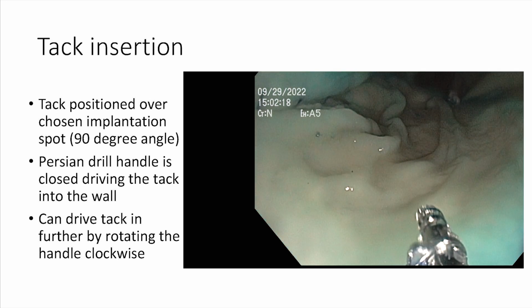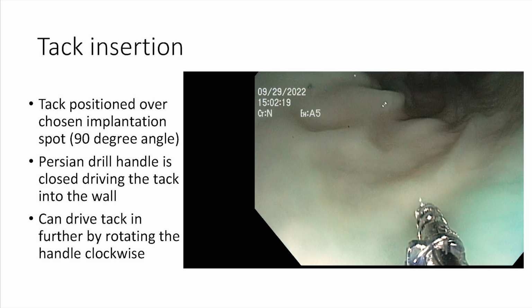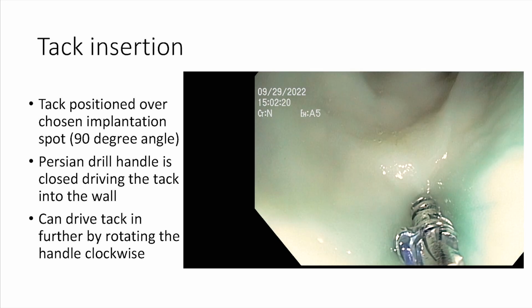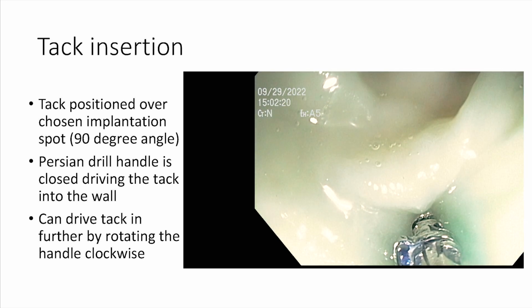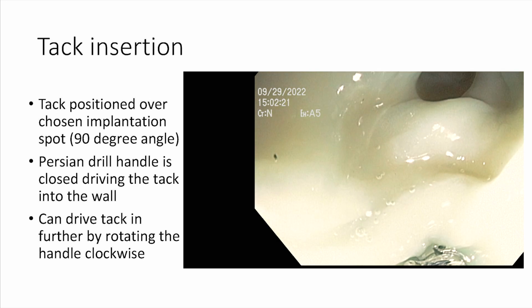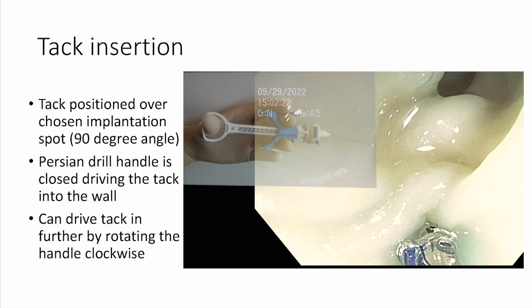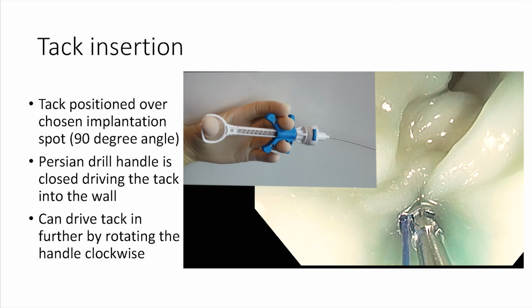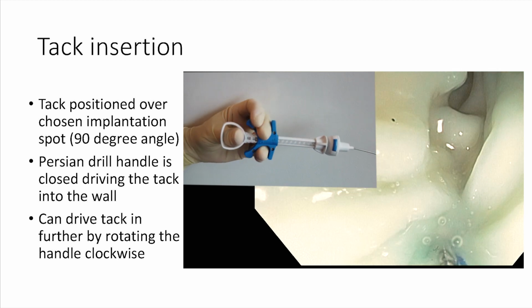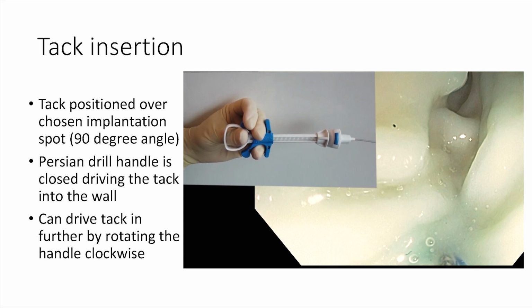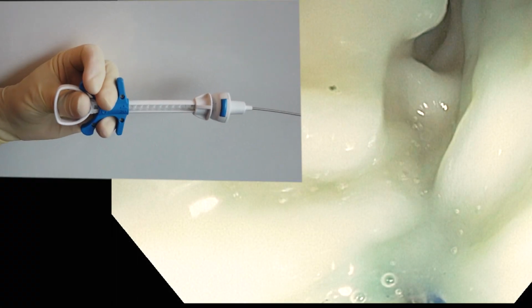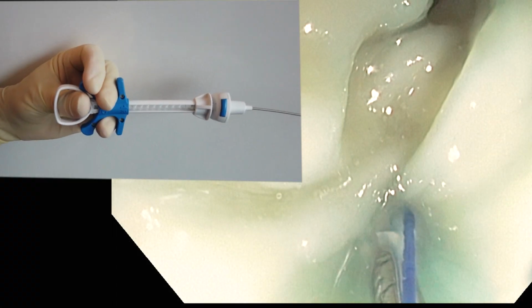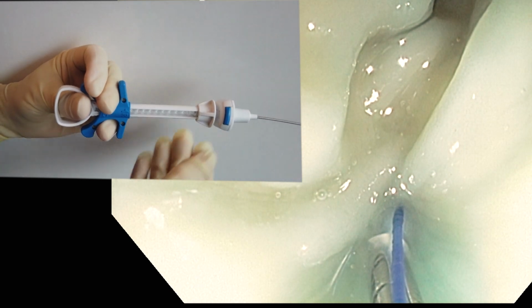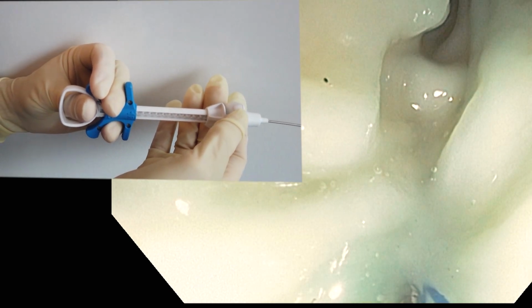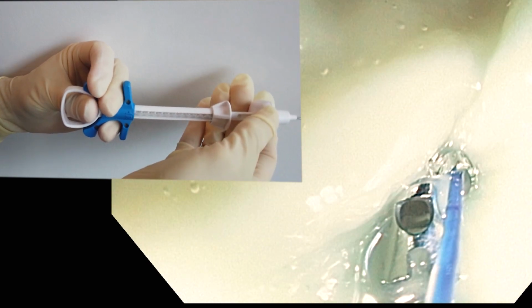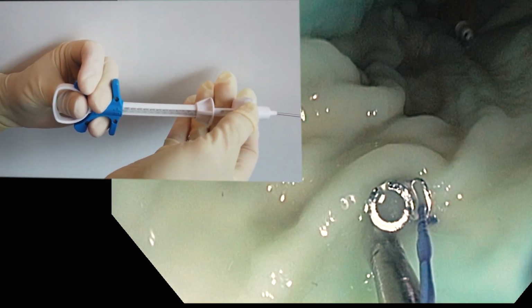At this point, the first tack can be inserted. To do so, the scope is positioned over the wound edge and the delivery device further advanced until the tack is being pushed with some force into the target area. Ideally, the tack should be 0.5 to 1 centimeter from the wound edge. On command, the assistant closes the Persian drill handle rapidly, which should screw the tack into the wall. Once inserted, to release the tack, the blue button on the proximal end of the handle is pushed down and slid forward while the rest of the handle is held steady. This separates the tip of the delivery device from the tack. The delivery device is then fully withdrawn from the endoscope.